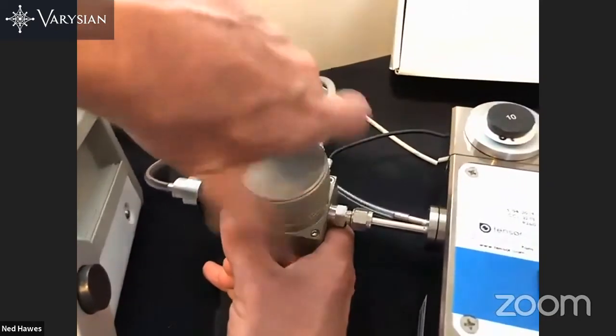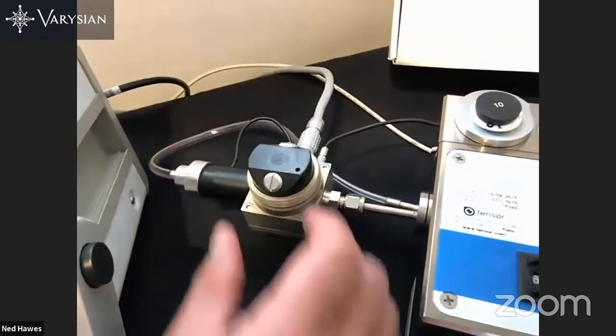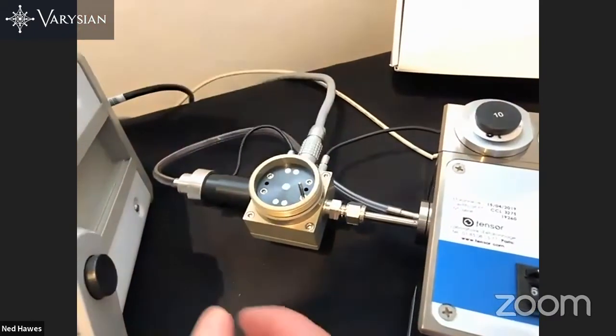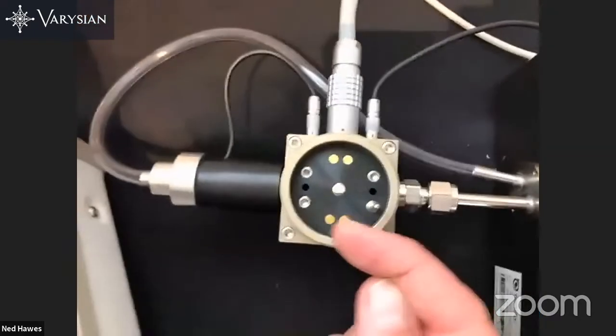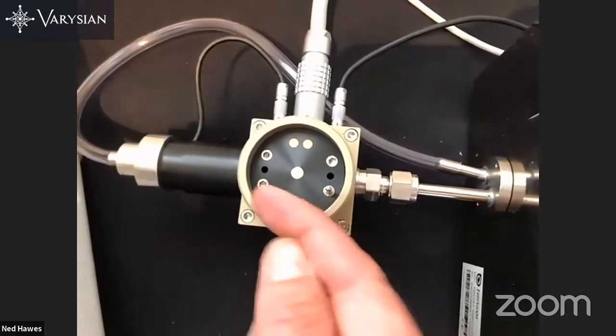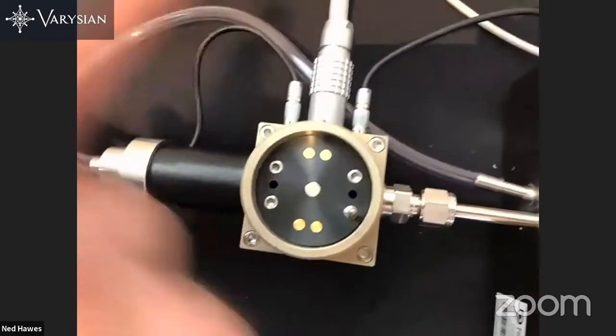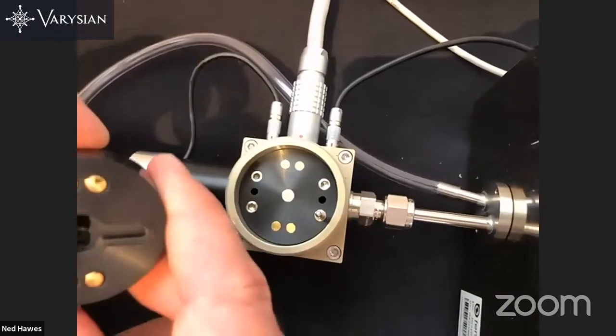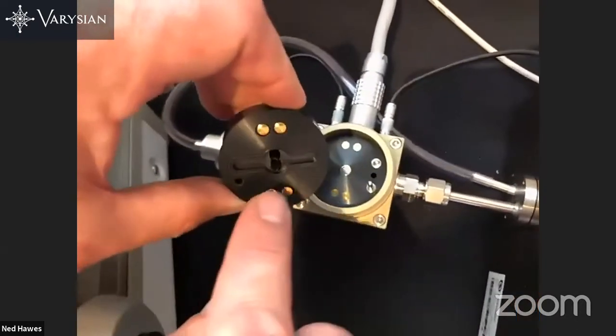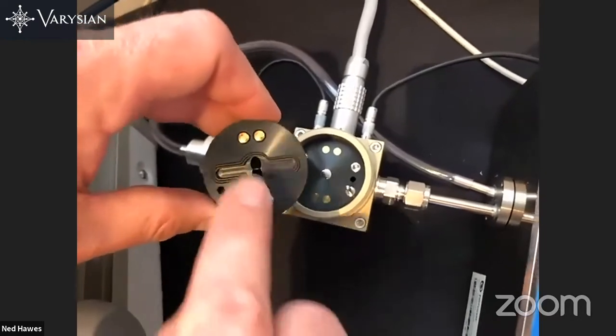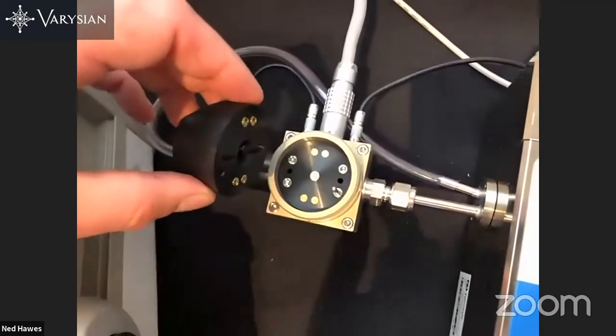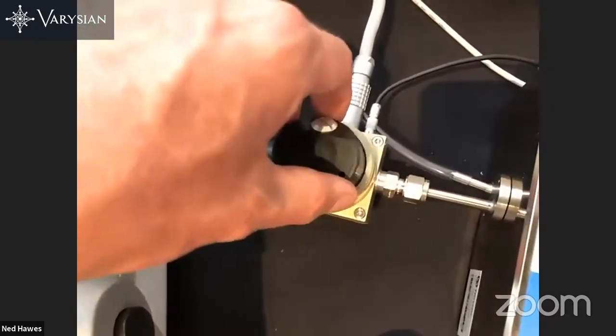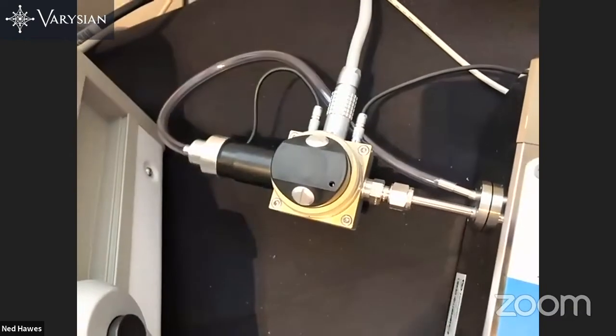Just to show you the top of the mirror: the gas comes through and over the mirror. You see the shiny mirror surface, the gas comes over that, is sucked through by a fan and then recirculated. Then we have an optical module with a photodiode and an LED, shining light onto the mirror and detecting the point at which the dew or frost film forms, and then measuring the temperature, which is the dew point.